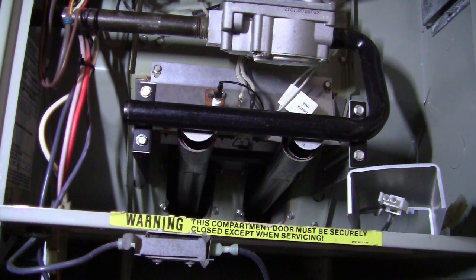Let me demo to you how I identified that my unit is not burning gas because of the controller, not the flame sensor. Even though I would replace the flame sensor, and it is required because it's old and broken, it doesn't finally fix the issue. So now let me demo how I identify that.